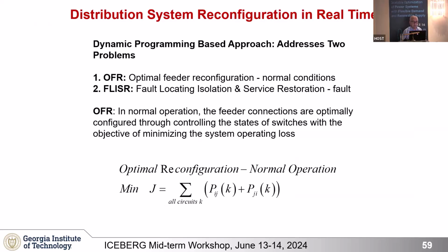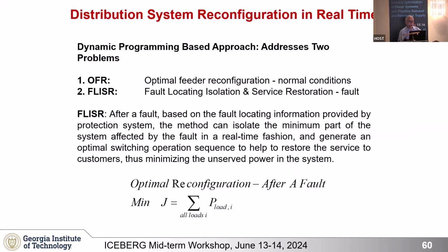So I'm going to focus on the OFR problem. Basically, optimal reconfiguration simply means minimizing the losses. If I look at any circuit in the distribution system, the sum of the real power flow into any element is the losses, and therefore the objective function is to minimize these losses. For FLISR, the objective is to maximize service, or minimize the customers affected. Here is one solution.